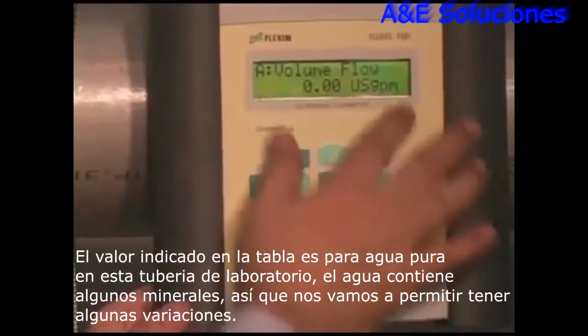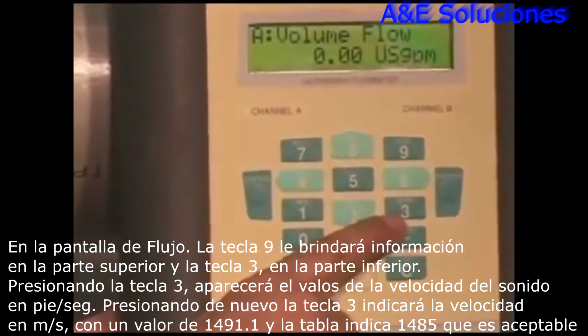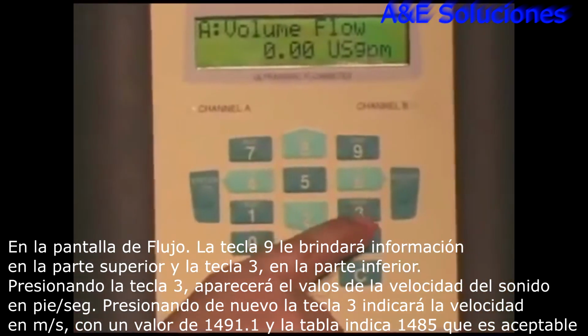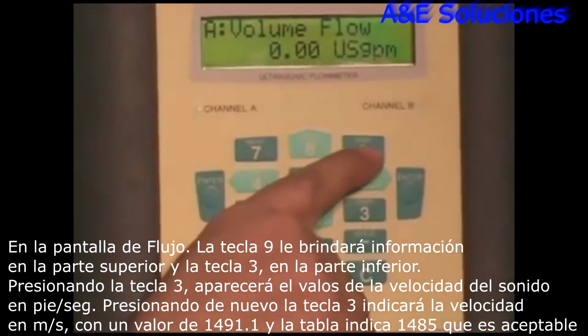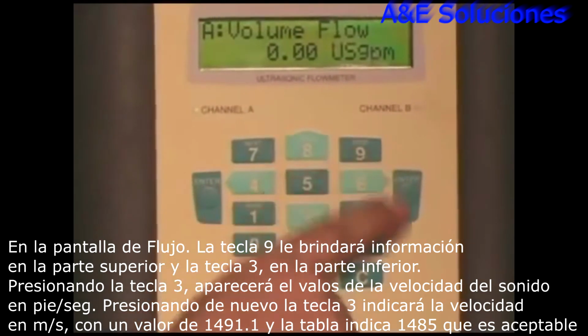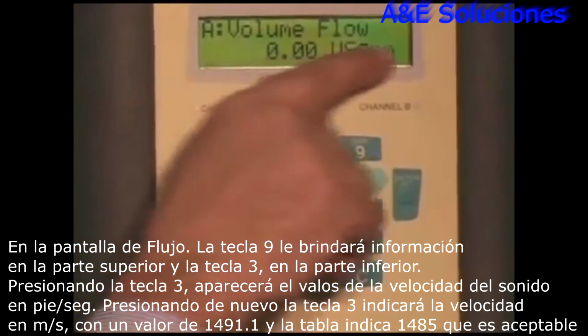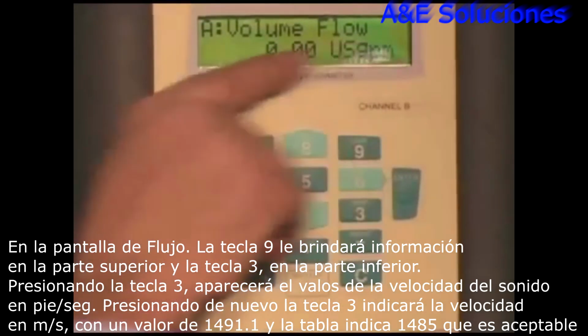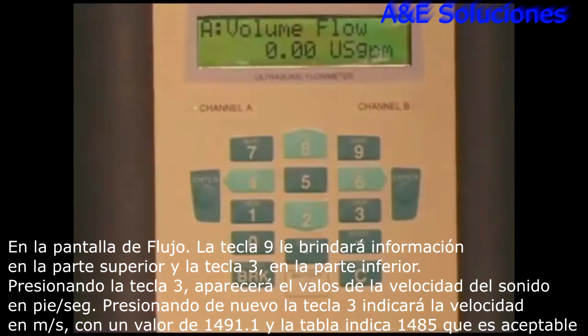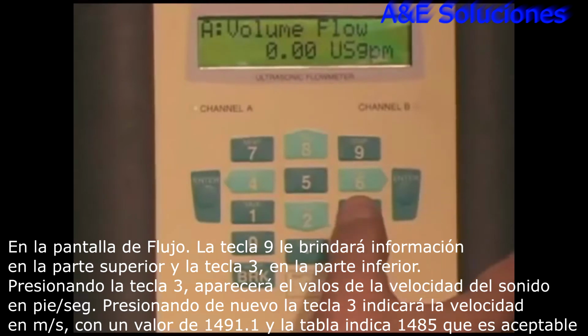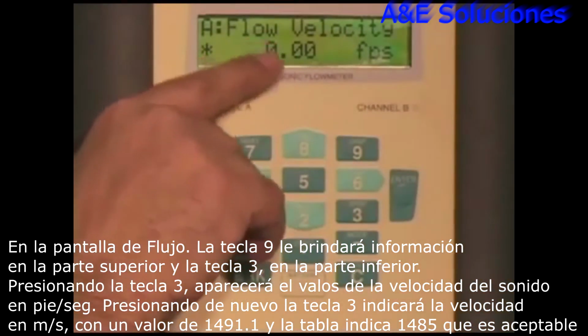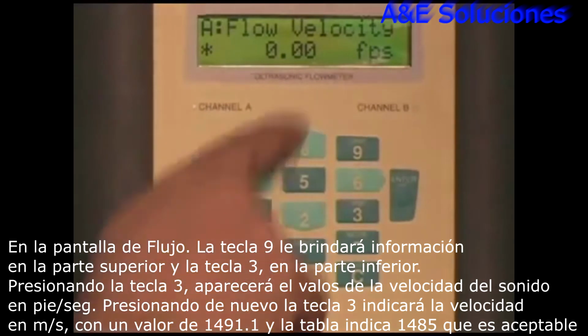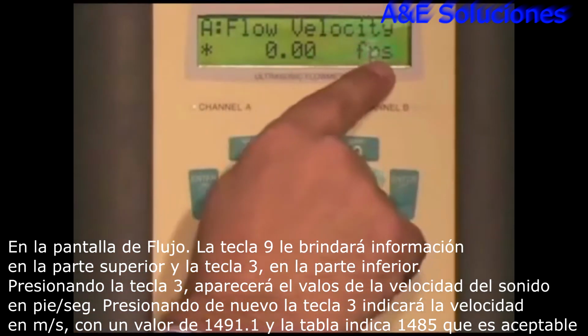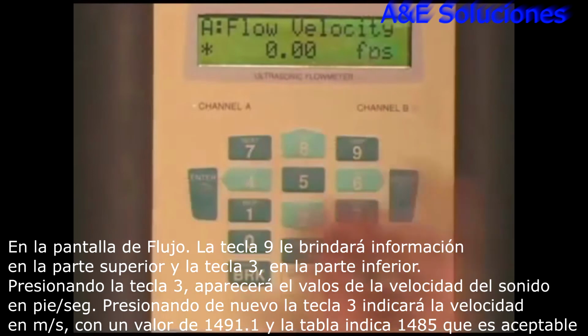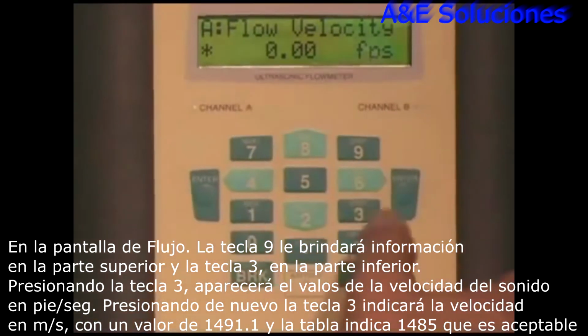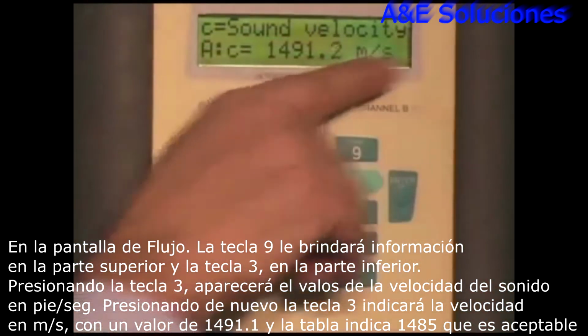Okay. Now when you're in the flow screen, over here the number 3 key, it says display, and along the 9 key here it says display. Now the 3 key will show you information on the bottom display, and the 9 key will show you information on the top display. So I'm going to hit the 3 key, and the first thing it tells me is flow velocity, so I can see what my velocity is in velocity terms. In this case here, feet per second, but if I wanted to see it in meters per second, I could change that unit. And now sound velocity of the liquid.